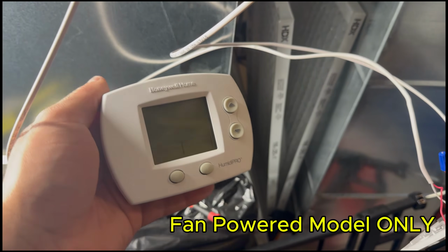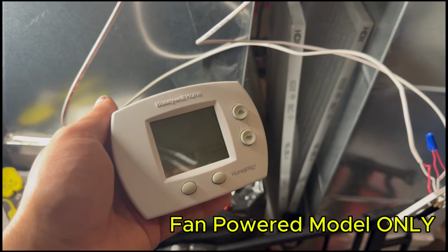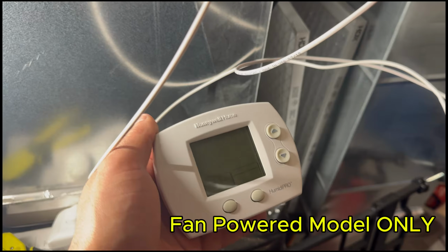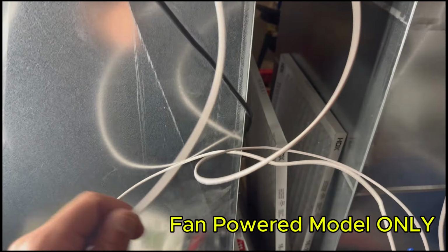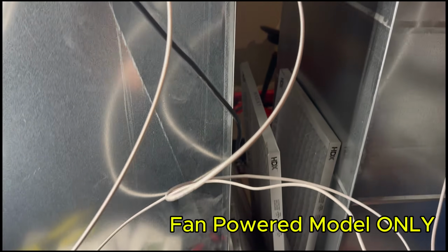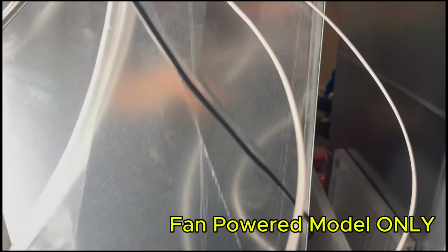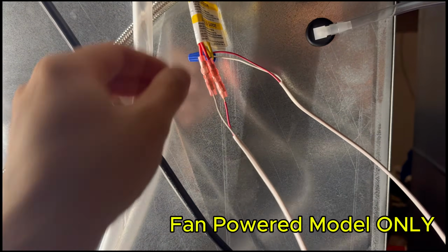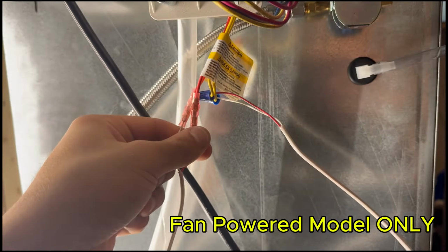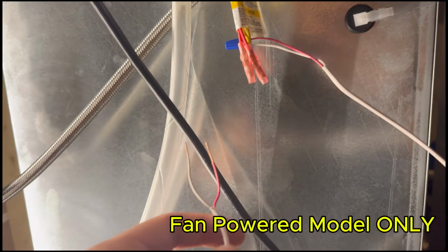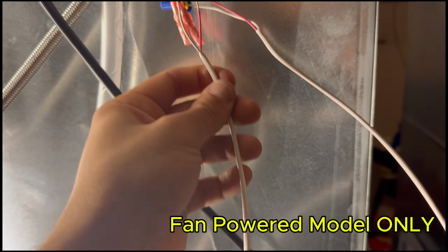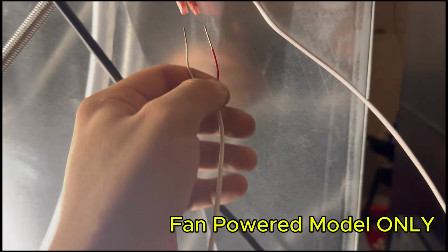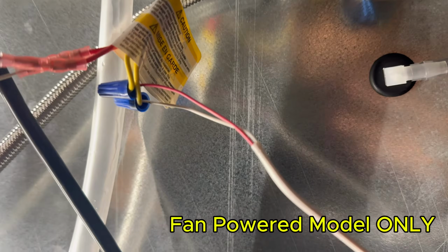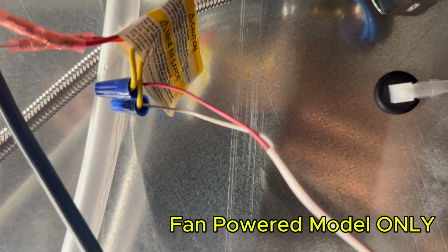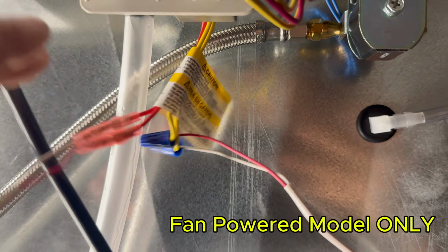Wiring on the electronic humidistat is a little bit more confusing, but I'll make it simple for you. You need 3 strands of low voltage wires, okay? The first one is low voltage wiring running from the 2 red terminals on your humidifier. So, 2 of them into the red terminals, leave the other end unconnected. The second strand of wiring is from the 2 yellow terminals on the humidifier. Leave the other end disconnected.